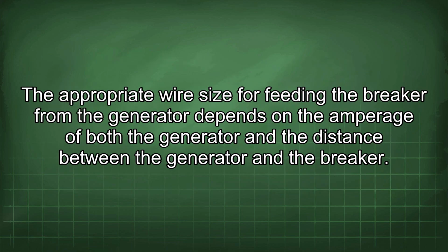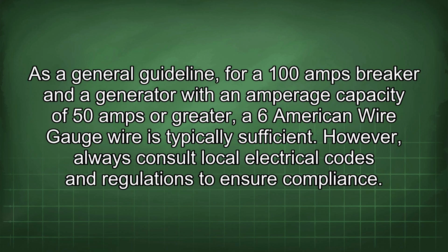The appropriate wire size for feeding the breaker from the generator depends on the amperage of both the generator and the distance between the generator and the breaker. As a general guideline, for a 100 amp breaker and a generator with an amperage capacity of 50 amps or greater, a 6 American wire gauge wire is typically sufficient. However, always consult local electrical codes and regulations to ensure compliance.